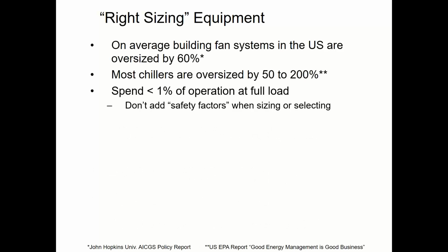We spend very little time at full load. So even if we did size something perfectly, which no one does, everyone oversizes, there are very few times of the year we actually would need it to operate that way. So what I need everyone to stop doing, literally everyone, is adding safety factors. Just size it correctly, trust your calculations, and move on. Don't add safety factors. Or at a minimum, don't add safety factors on your load calculation software inputs.